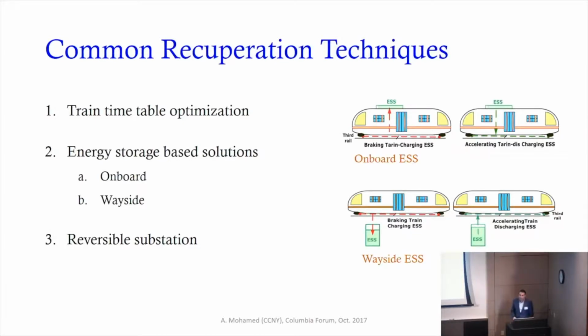Even though the trains that are capable of using regenerative braking produce energy every time they brake or decelerate, it doesn't necessarily mean you will be able to put this energy on the third rail or on the line and make use of it. The reason is that this energy is huge, and unless there is a load as close to the decelerating train, the voltage will go up, and the protection system will dump this energy into resistors as heat.